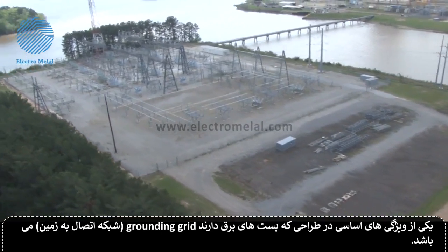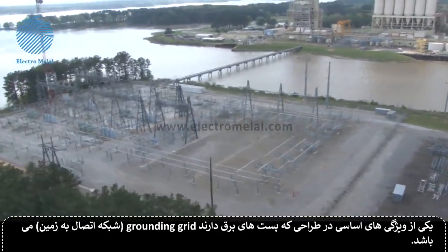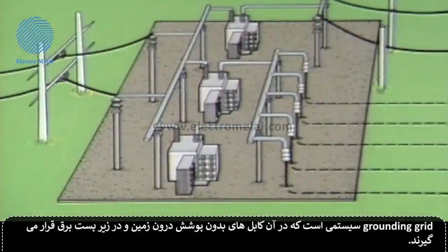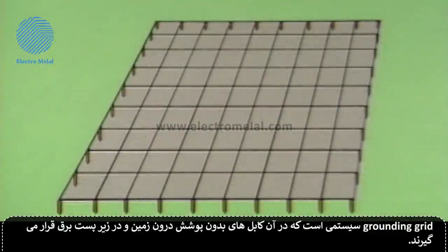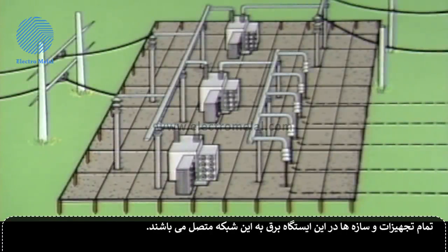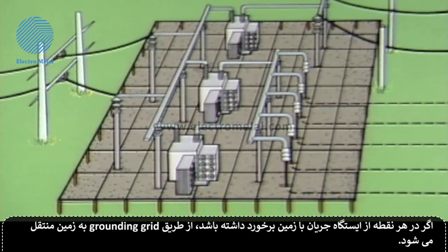One basic design feature that substations have is a grounding grid. A grounding grid is a system of bare cables that is buried beneath the substation. All the equipment and structures in the substation are grounded to the grid. If there is current flow to ground anywhere in the substation, it is dissipated to the earth through the grounding grid. Of course, you can't see the grounding grid because it's buried.